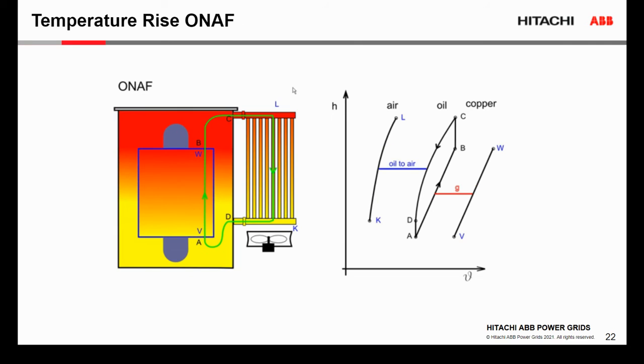To improve the air circulation around the transformer, we install the fans, and in this case, most of the time the transformer has ON cooling only up to 60% of the rated power, and then we have two additional stages where we turn on fans, like first stage of ONAF cooling, when we turn on the first group of fans, and then at the full MVA, we turn on the second stage of the cooling. And the fans are controlled by the temperature gauges.